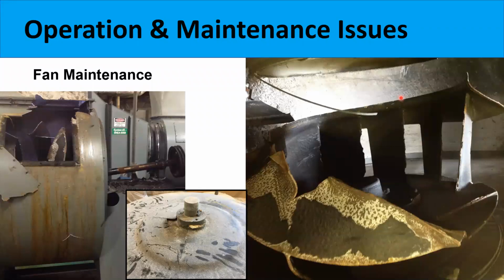This example is a catastrophic failure of a backward inclined centrifugal exhaust blower wheel. The situation got out of hand with excessive vibration that went unchecked, and essentially had a wheel moving at a very large RPM, probably in the 2,000 to 3,000 RPM range, begin to fly apart and shoot shrapnel through the fan housing here on the left. Very dangerous situation. If there's personnel in that area, it could cause serious injury. And so it's just best to keep these things in check by monitoring. We'll get into monitoring a little bit further here soon to prevent a catastrophic failure of these fan wheels and shafts.